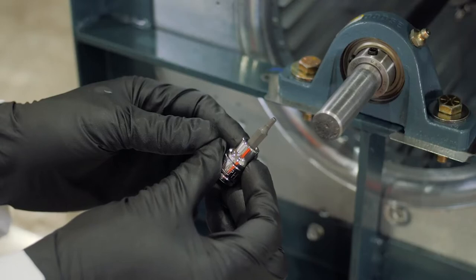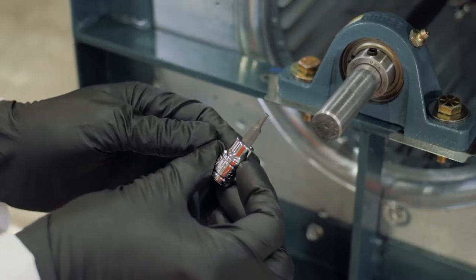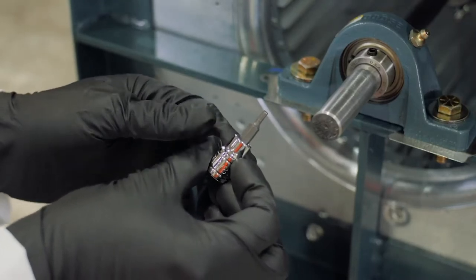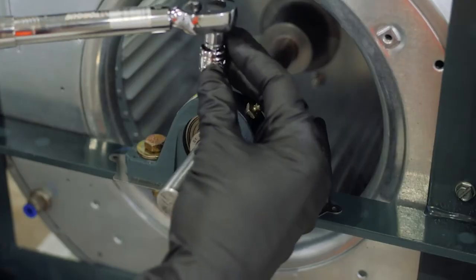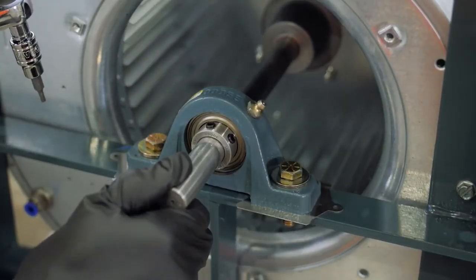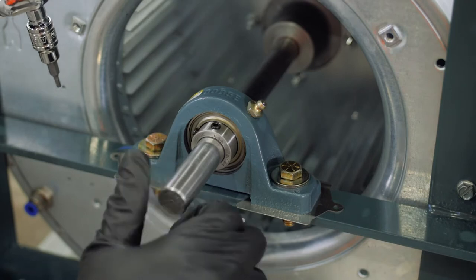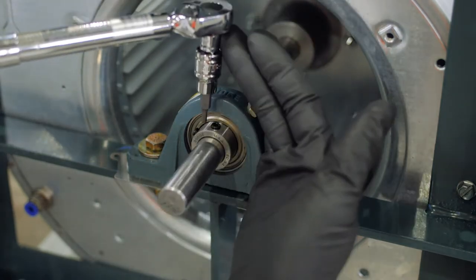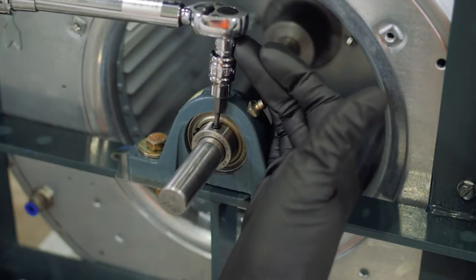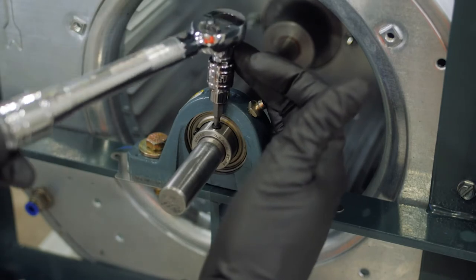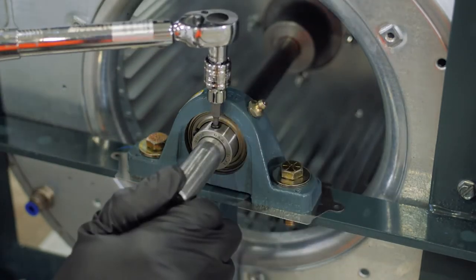To achieve proper installation torque, ensure the hex driver is in good condition with no rounded corners. To prevent rounding, the hex driver should be fully seated and perpendicular to the set screw during tightening. Use your second hand to firmly hold the head of the torque wrench to ensure full engagement and perpendicularity.